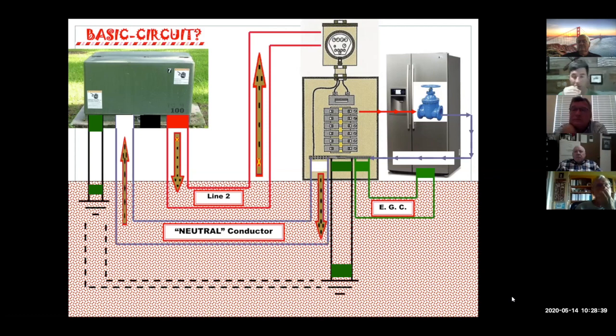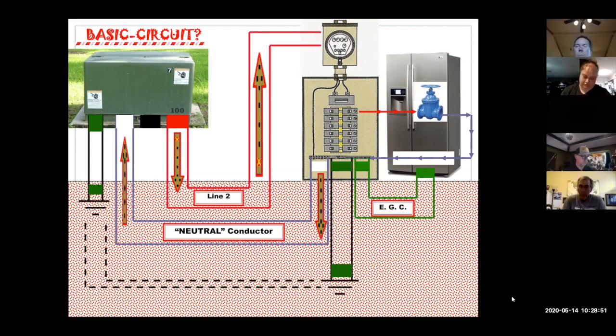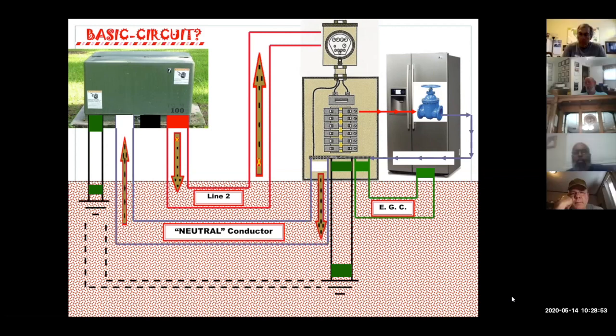If it's your body, your resistance, if you're wet, is going to be 100 ohms of resistance is what we use. And in death cases, we use 500 ohms as the valve, if you will, or the load that the victim gets in series with and goes through their body and can hurt or kill.